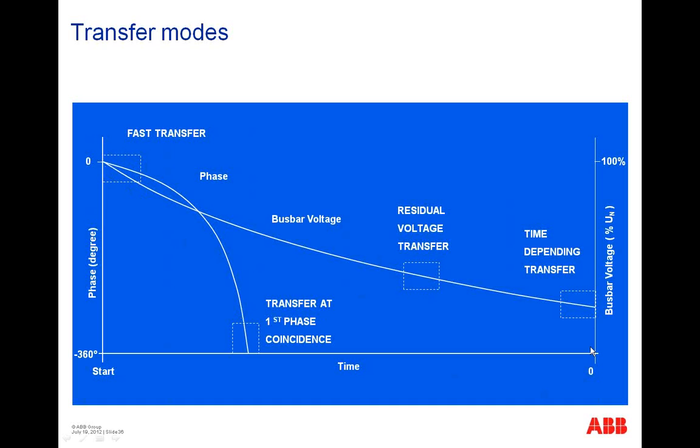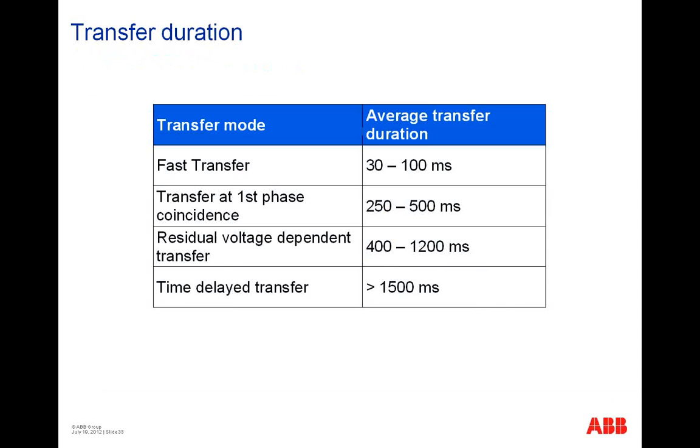Here we keep everything alive, and with the ATS functionality, called time-dependent transfer, you will lose everything on your bus bar, on your processes, and have to restart everything in your facility, in your industry, and it takes some hours up to a day, and you have big trouble until everything runs again very well. So that you get an idea when we're talking about transfer.